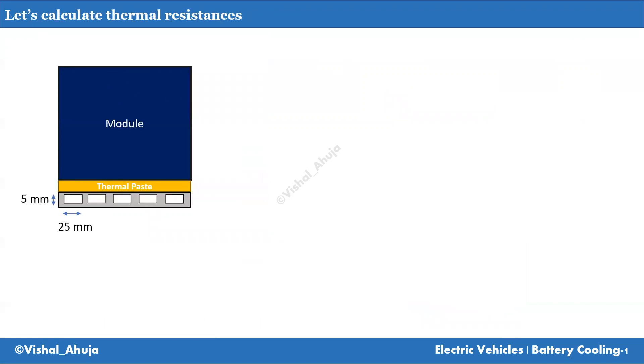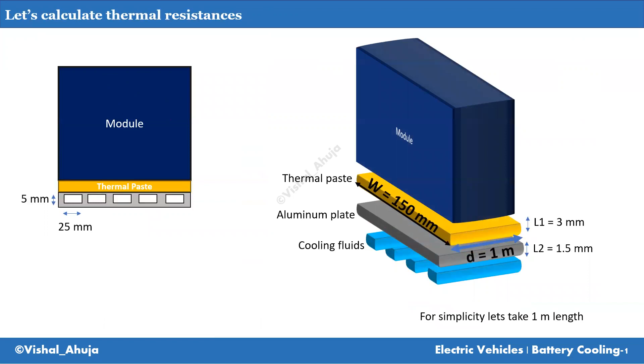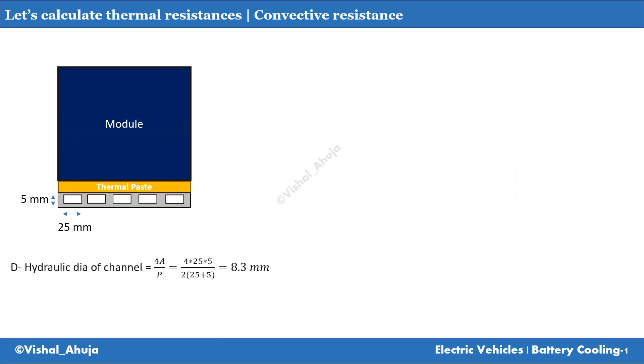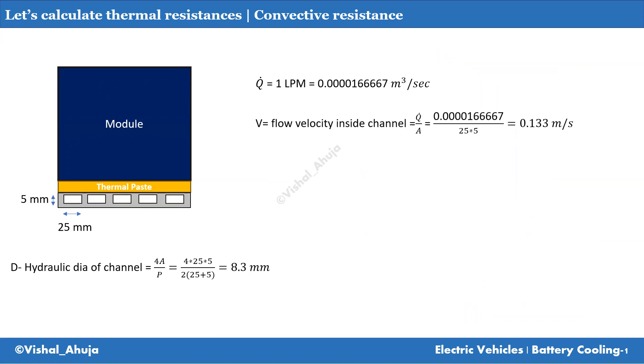For this consideration, let's consider one channel has a cross section of 5 mm by 25 mm. In the 3D geometric representation, consider 150 mm as the width of that section. We have a thermal paste of 3 mm thickness, below which there is a 1.5 mm thick aluminum plate, below which there are some cooling channels. For simplicity, we are taking a 1-meter depth of the system. Let's calculate the hydraulic diameter, then for 1 LPM flow in one section, we calculate the flow rate and velocity in that channel.